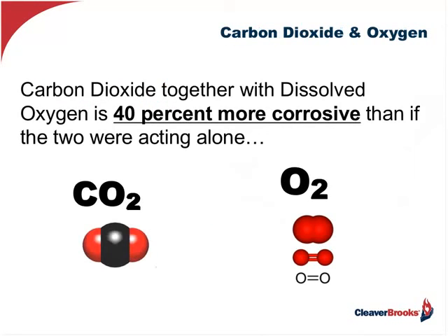And also carbon dioxide, when put together with dissolved oxygen, is 40% more corrosive than if the two were acting alone. So now you combine the two, and you've got double jeopardy here.